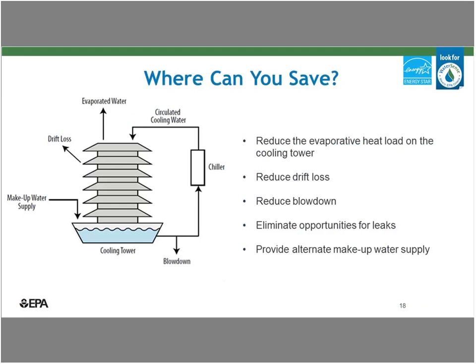So we just talked about some of the water inputs and outputs from the tower, but what we're really interested in is where we can save water. So to save water, you can either reduce the evaporative heat load on the cooling tower, reduce drift loss, reduce system blowdown, or minimize leaks or propensity for leaks. This is sometimes just an unintentional form of blowdown. And then you can also provide makeup water from a source other than city water.